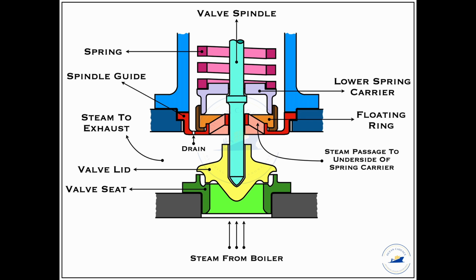because it is often found that in ships that are relatively older in age, the easing gear is often found in dilapidated condition. One of the common defects that occurs in the easing gear is that there are kinks in the cables, or the valve head, that is the cap side where the easing gear operates, is often stuck in its place or has gathered rust or salt deposits that can lead to ineffective operation of the easing gear.